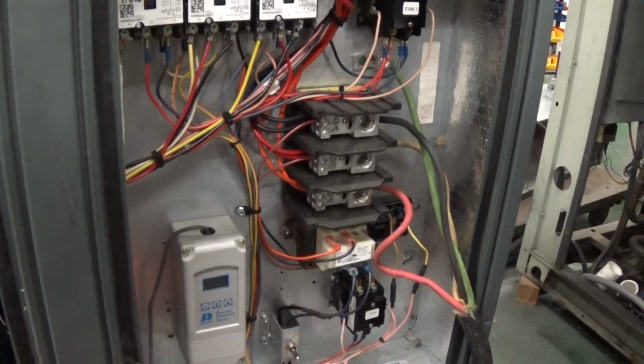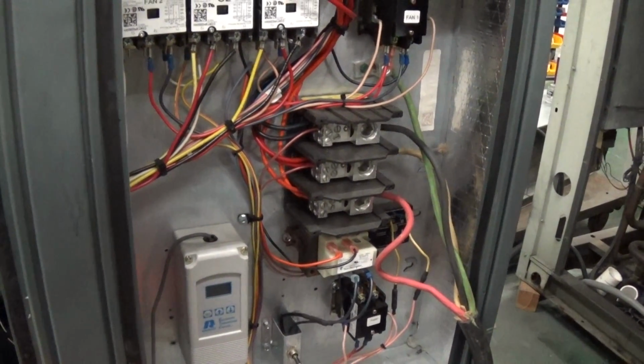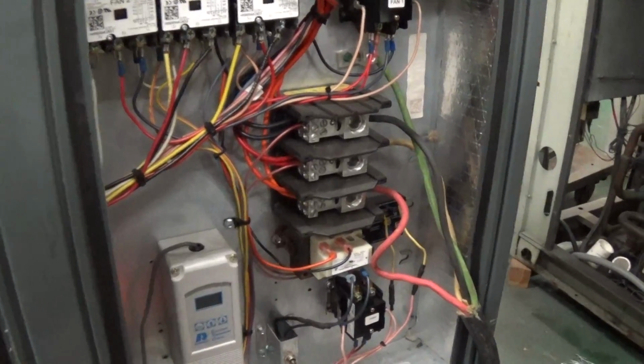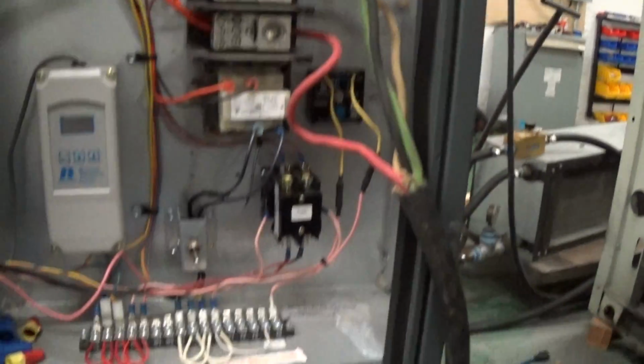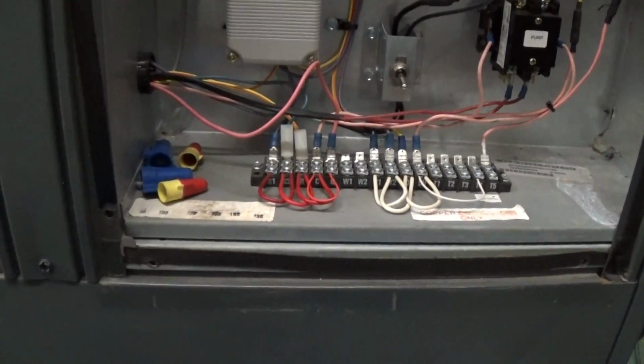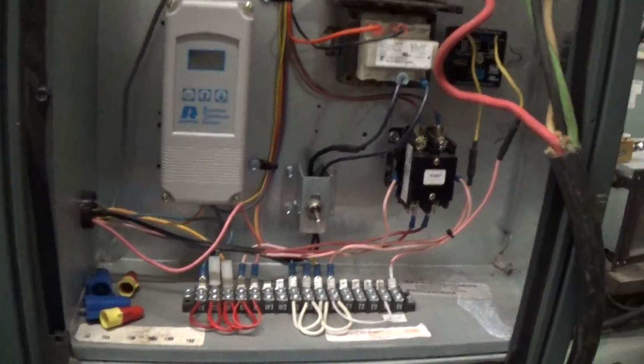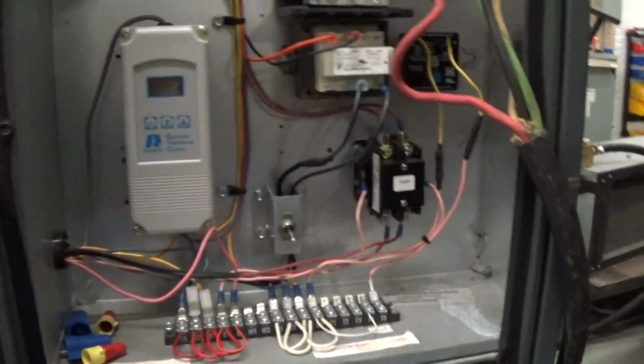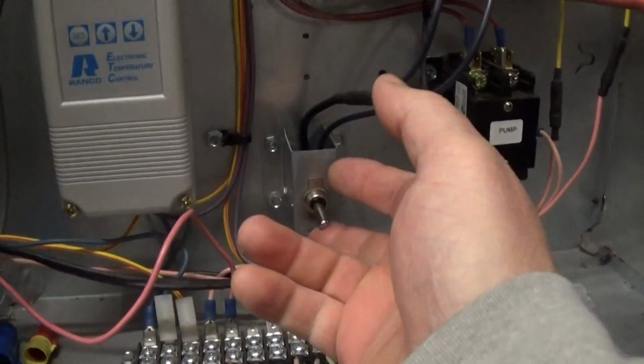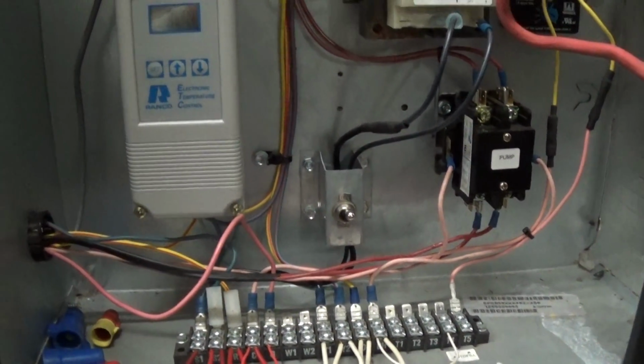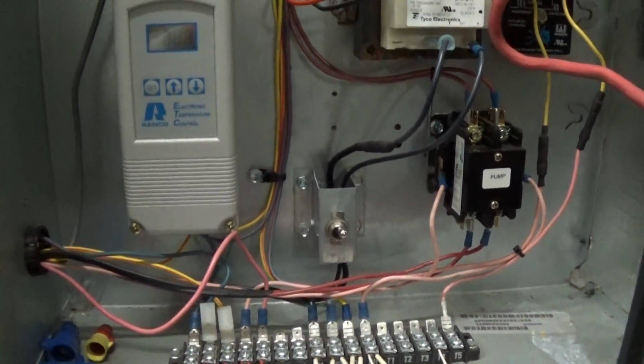And then while it's starting to chill, I'm going to go around and talk about a few different things on the unit also. So these are outdoor rated units. The controls and the electrical are all within this sealed cabinet door, which should be on. To turn the chiller on, all you do is come over to the toggle switch here and turn the switch up to turn it on, and that basically activates the pump.